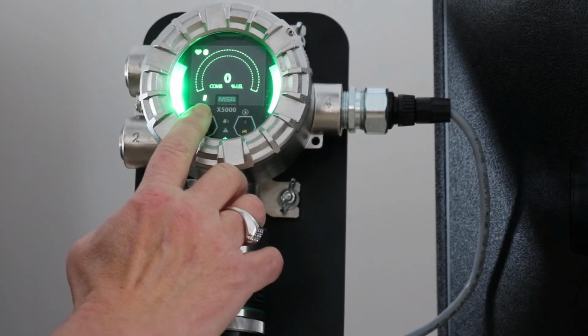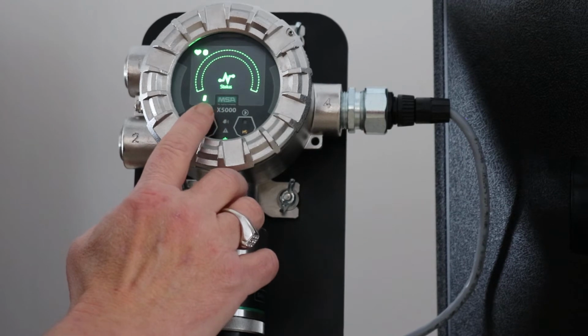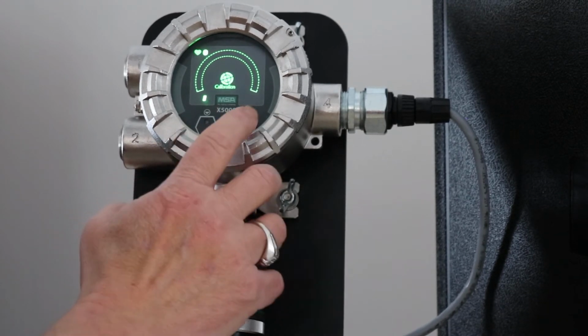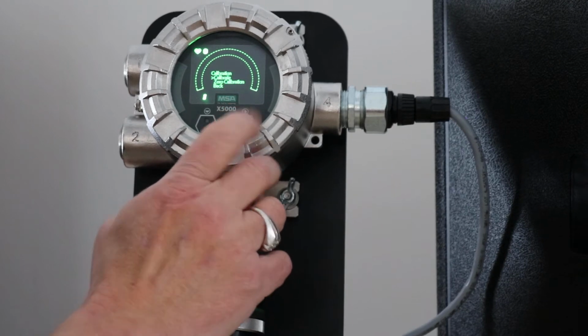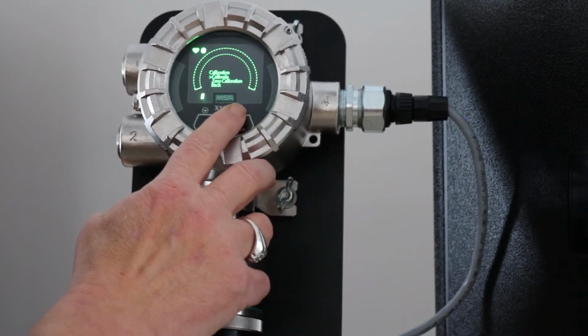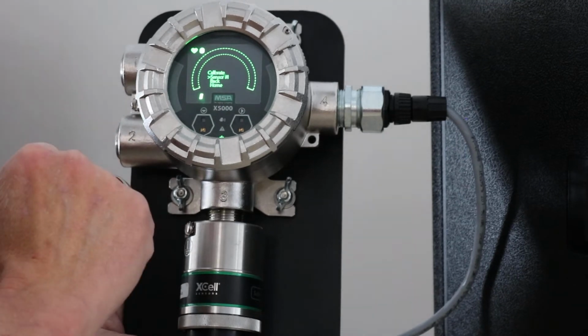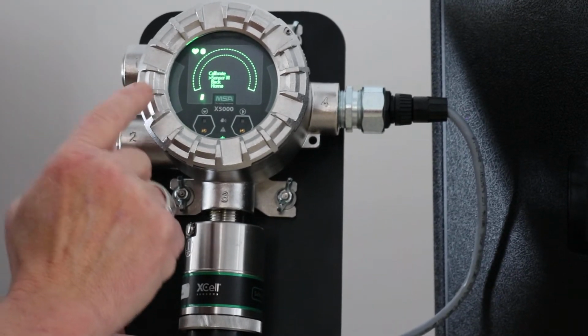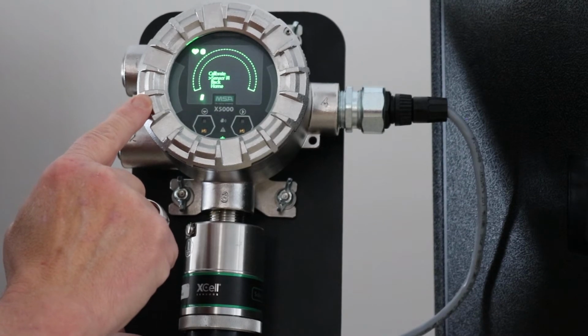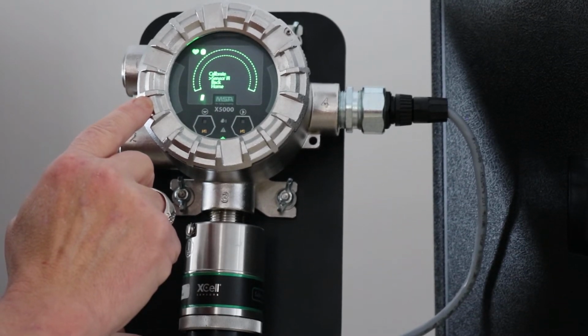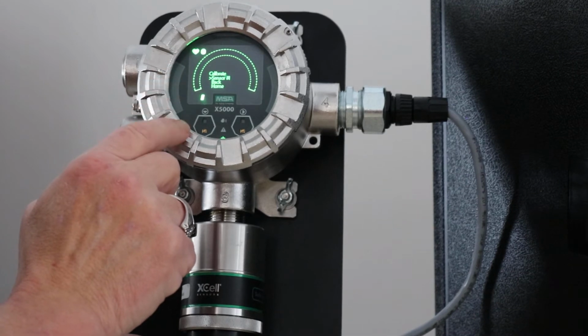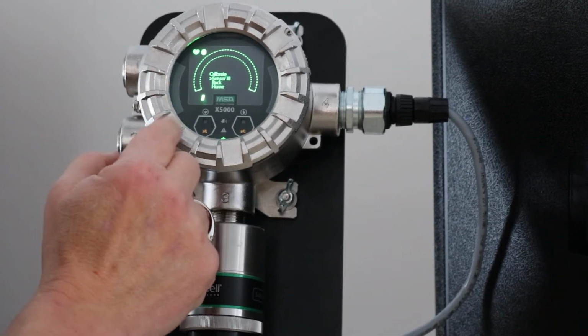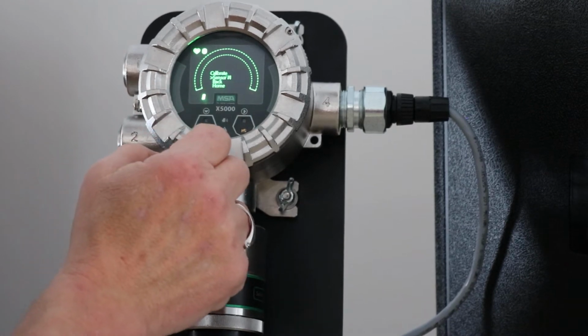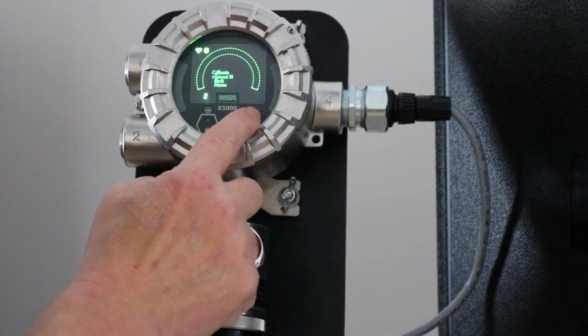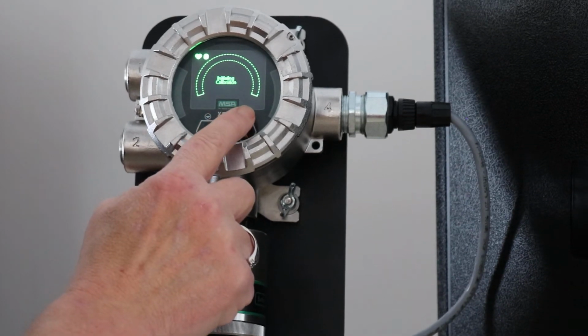Alright, and with that, if you go up and hit the left button, the first one is status, second one is calibration. You hit the right button and it goes into calibrate. Hit it again and it says calibrate sensor number 1. Now this device, this transmitter can have two sensors on it. So if you're going to calibrate the second sensor, you simply press the left hand button to scroll down to sensor number 2. In this case, again, we only have one sensor. So it says sensor number 1 with a little arrow next to it. So I will press the right button, which gets us into the calibration mode.